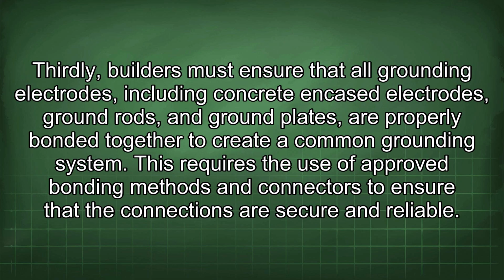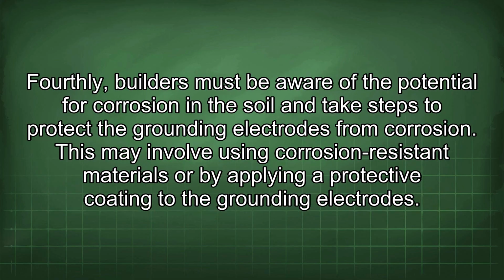Thirdly, builders must ensure that all grounding electrodes, including concrete encased electrodes, ground rods, and ground plates, are properly bonded together to create a common grounding system. This requires the use of approved bonding methods and connectors to ensure that the connections are secure and reliable. Fourthly, builders must be aware of the potential for corrosion in the soil and take steps to protect the grounding electrodes from corrosion. This may involve using corrosion-resistant materials or applying a protective coating to the grounding electrodes.